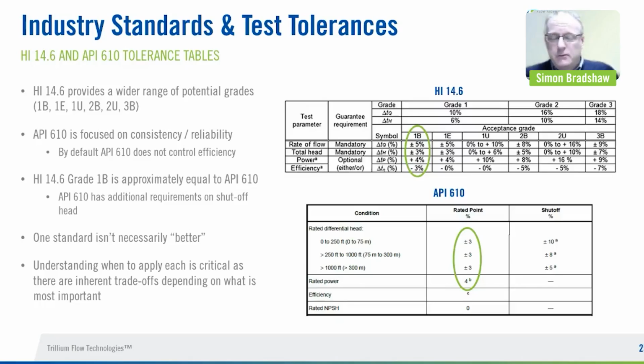And the reason for this is that API 610 historically was focused on consistency and reliability. By default, API does not control for efficiency. That was not something they were considering. They do control for rated power, but that's mainly to ensure you don't overload the motor. They were never historically interested in efficiency. On the flip side, some of the HI tolerances are very much focused on efficiency, as you'll see later.